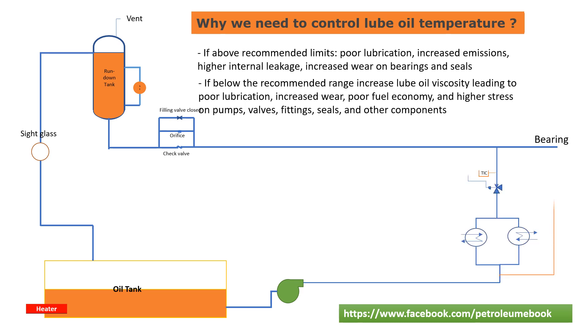To keep lube oil temperature stable, we normally use three-way temperature control valves, also known as thermostatic control valves (TCVs) or temperature regulators. These use self-actuating thermostatic technology to monitor the inlet flow and divert the fluid based on temperature. Cooler fluid will go through the bypass of the valve directly to the reservoir or bypass loop.